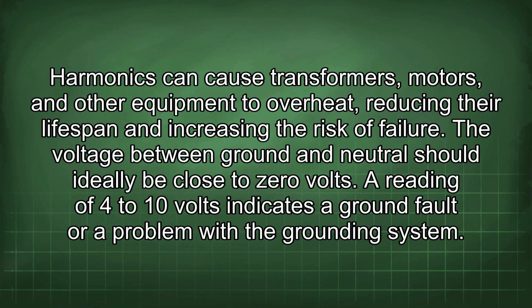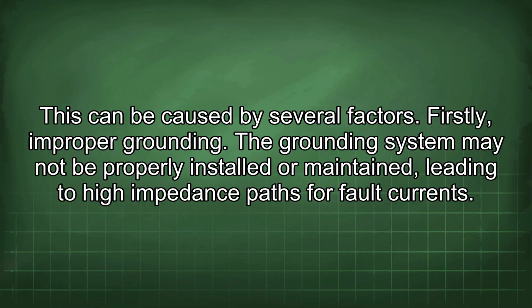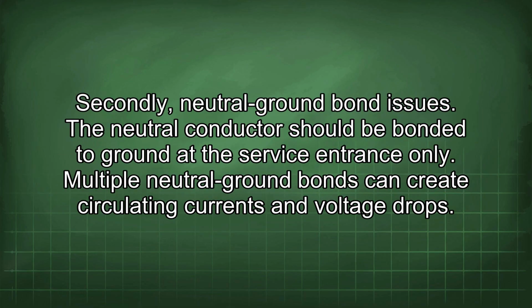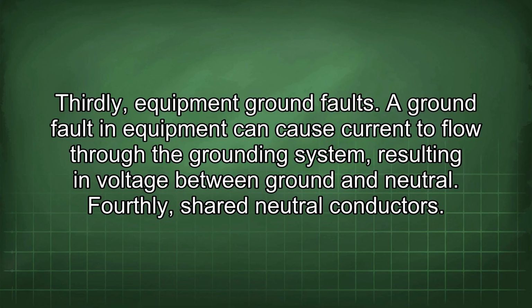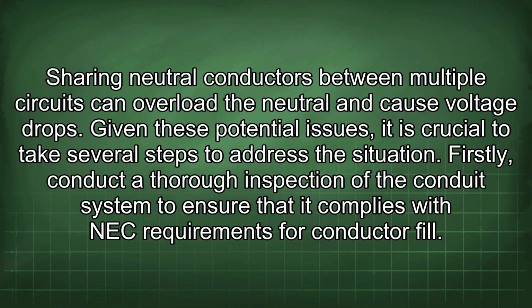The voltage between ground and neutral should ideally be close to 0 volts. A reading of 4 to 10 volts indicates a ground fault or a problem with the grounding system. This can be caused by several factors. Firstly, improper grounding. The grounding system may not be properly installed or maintained, leading to high impedance paths for fault currents. Secondly, neutral ground bond issues. The neutral conductor should be bonded to ground at the service entrance only. Multiple neutral ground bonds can create circulating currents and voltage drops. Thirdly, equipment ground faults. A ground fault in equipment can cause current to flow through the grounding system, resulting in voltage between ground and neutral. Fourthly, shared neutral conductors. Sharing neutral conductors between multiple circuits can overload the neutral and cause voltage drops.